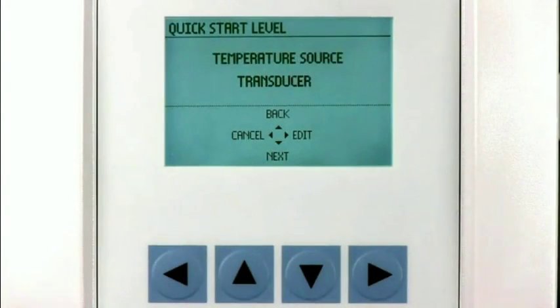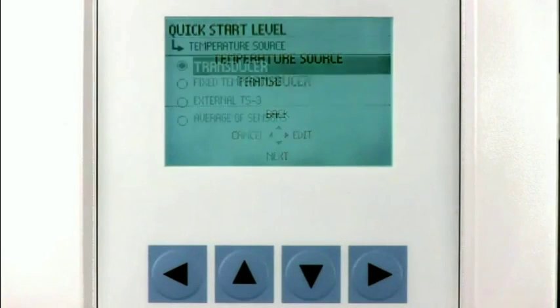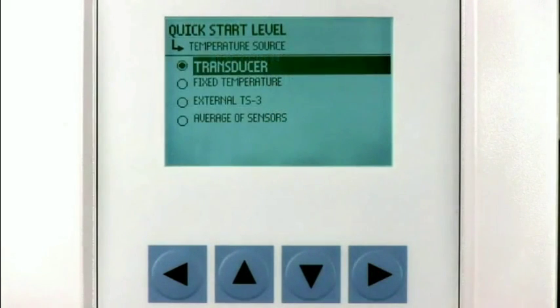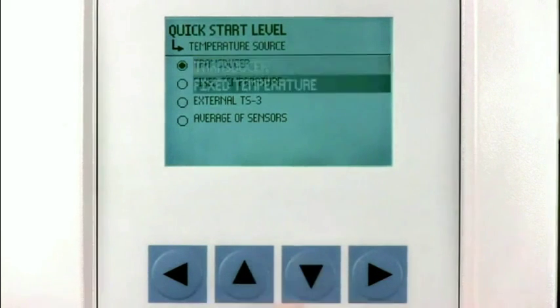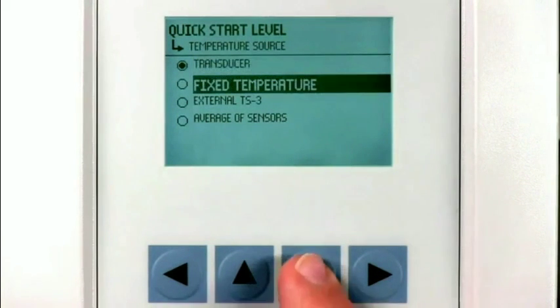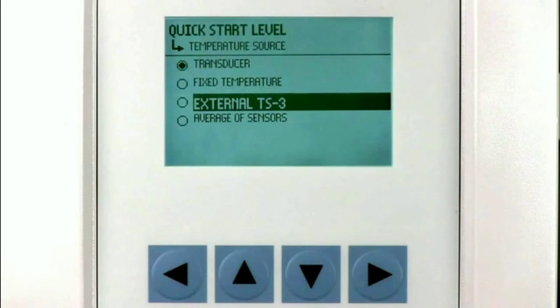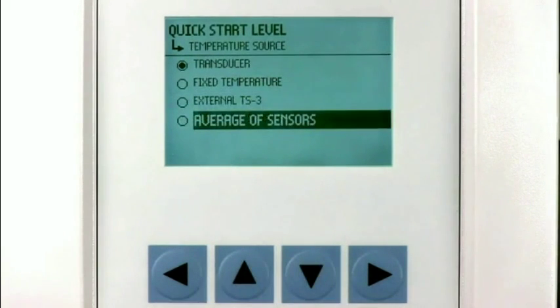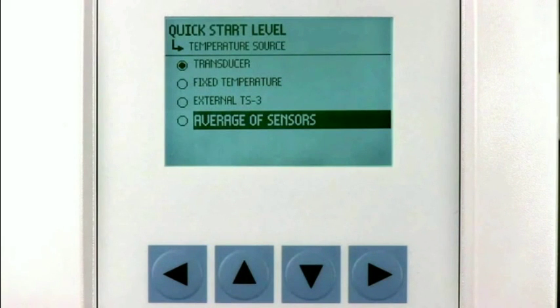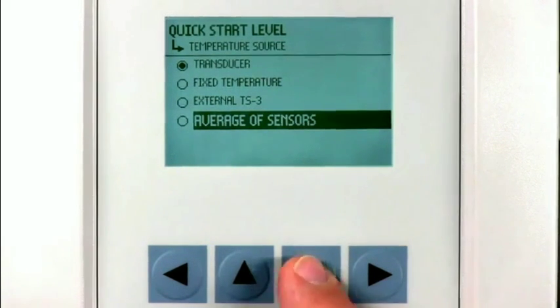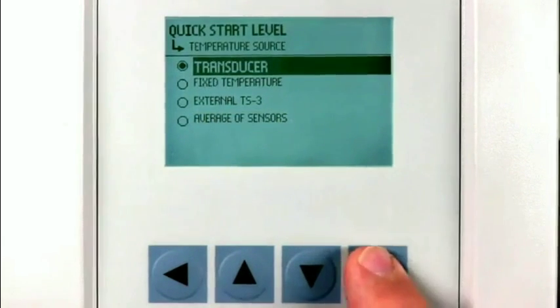The LUT400 uses a temperature sensor to automatically adjust for speed of sound changes within the measuring atmosphere. We can use the sensor built into the Echomax transducer or an external TS3 temperature sensor. Another option is the average of both the transducer temperature sensor and the TS3. We will use the transducer selection for our application.